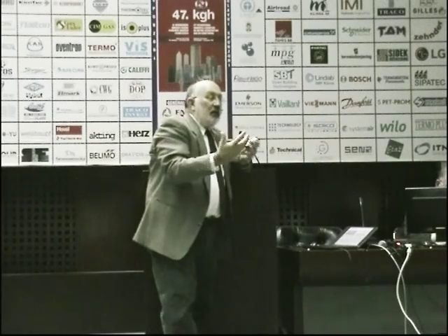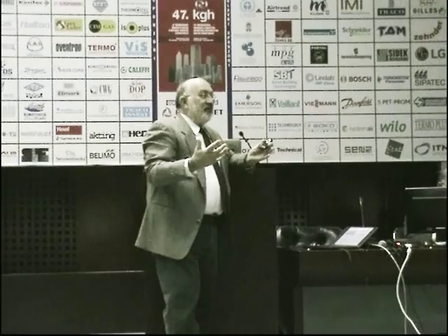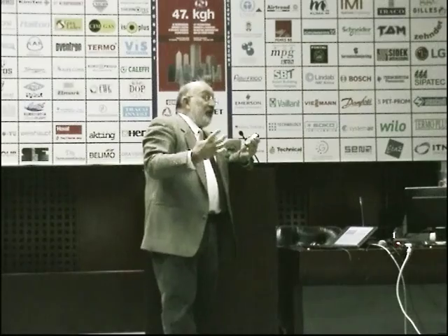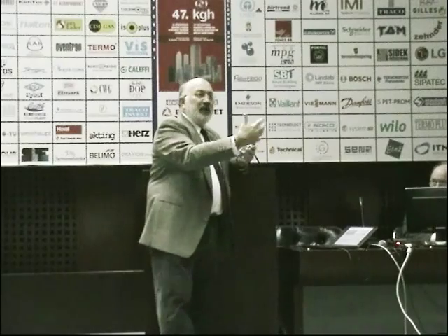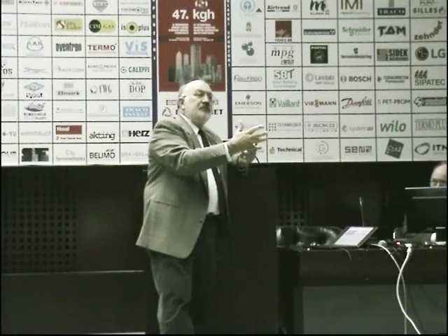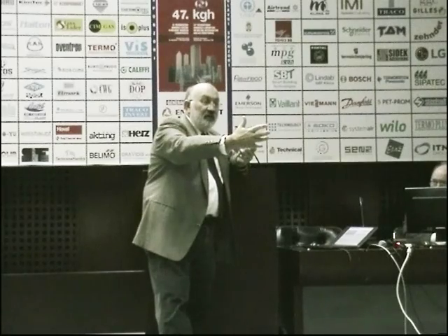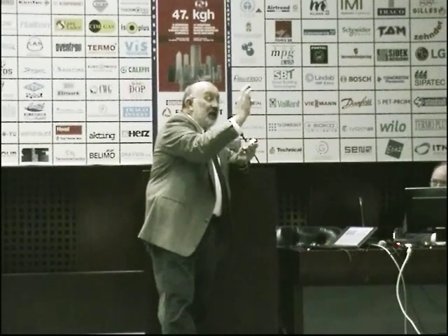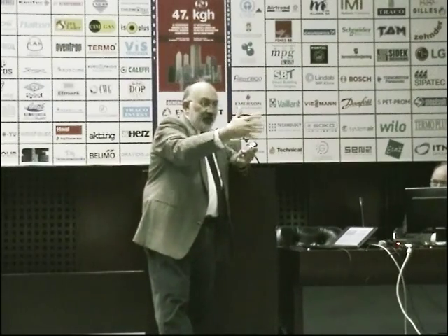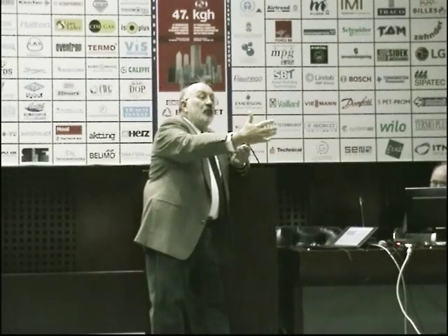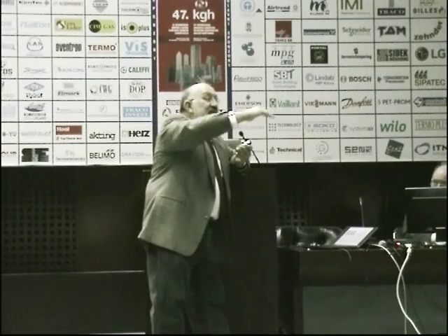And that typically is always the question: now when I understand the physics more or less, I have some concept, what is the reality? Because if I want to build a compressor, if I want to build the separator, the question is then, how long is that? Typically, in the normal smaller compressors here, where discharge velocities are between 10 and maybe 20 meters per second, the size of a discharge pipe is appropriate for the flow rate. It typically takes between 1 meter and 2 meters to come to that equilibrium point.